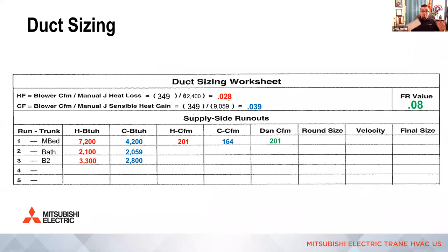So we would walk through the same for the bathroom, right? We would do the multiplication. I personally like to figure out all the design CFM and then run through size. But in this example, if we were going to line up 0.08 for friction rate to the volume of air we need, 201, you're going to find that it falls just in between 7 and 8 regarding the round size.